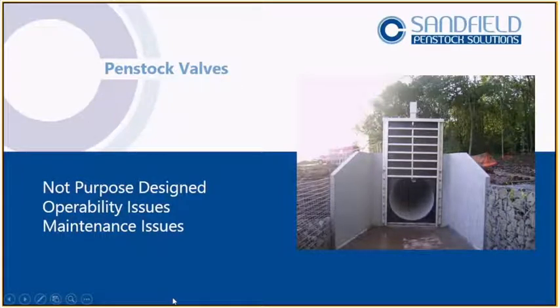There are also major maintenance issues. When a penstock is down in a chamber with a manhole cover over it, you can't actually get that valve out without completely removing the cover — that's a civil project that could cost thousands of pounds. And monitoring: penstocks have a tendency to require mains power, but you normally want pollution containment valves at the end of a site where there's no mains power. What we tend to do instead is use basic monitoring and M2M controls — ping it out to one of our valves in the middle of a field with a solar panel, and we can control massive sites with quite simple technology. The penstock valve is very slow, cumbersome, and always needs mains power.